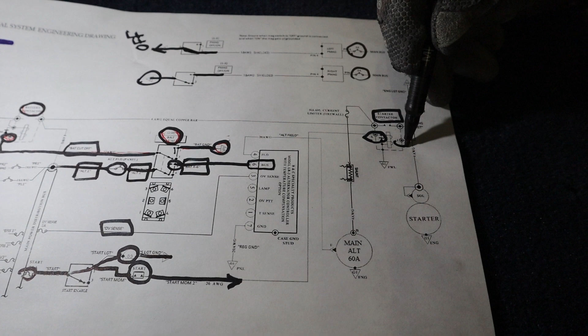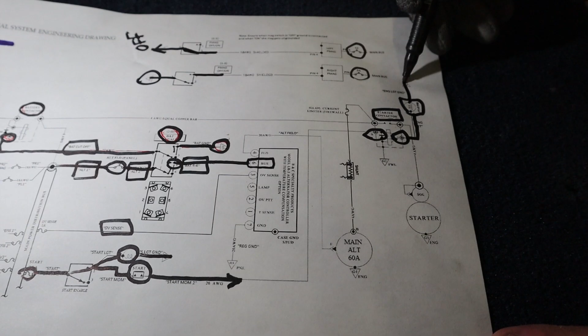From the back of this switch, once we go up and energize the light, it's also going to energize the circuit that goes to the start switch, which is a momentary button. The other side of that start switch, according to our diagram, goes to the terminal point on the starter relay. Remember, we ignite the starter relay through power, and we energize the master relay using ground. So if I push that switch right now, it's going to energize the starter.